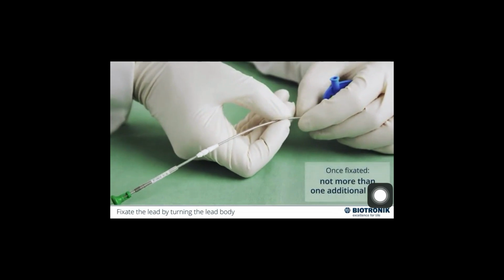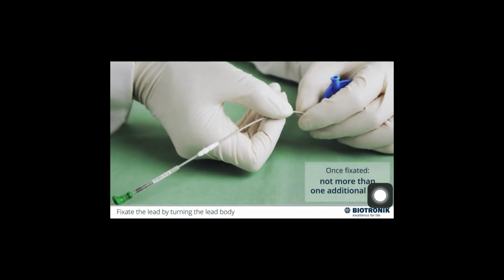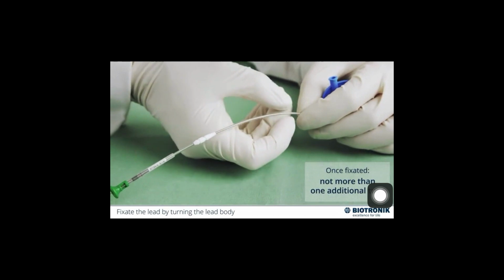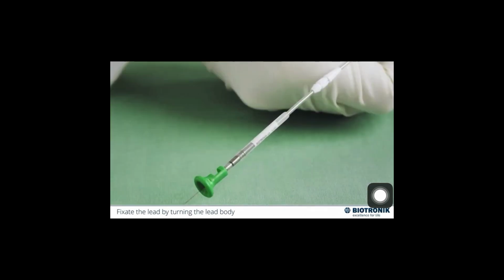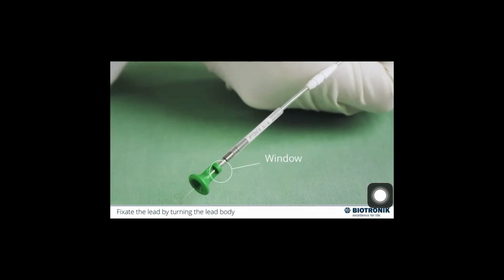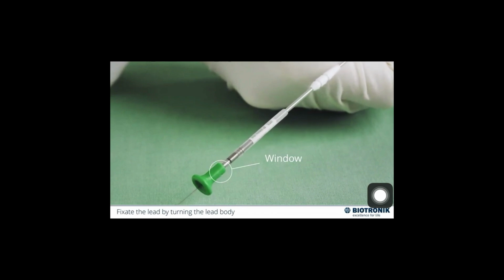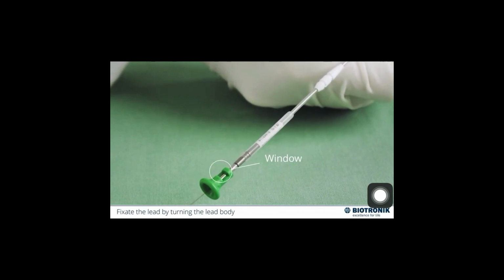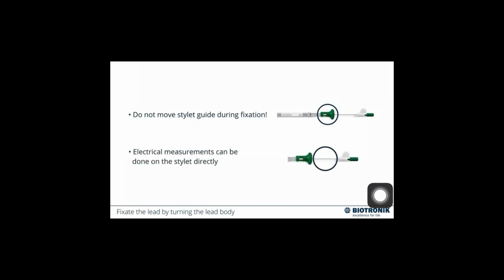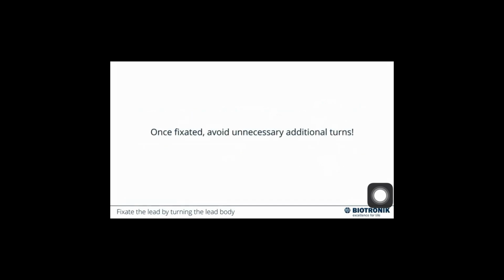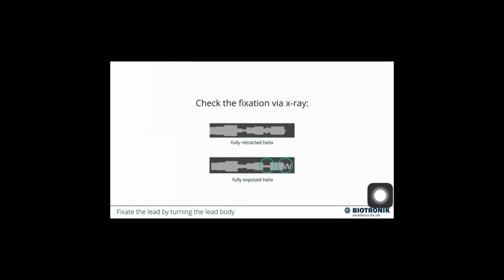Once the physician is comfortable with the lead fixation, he or she can do 1 additional complete turn, but not more. Full turns can be counted by looking at the window on the green stylet guide. In order to keep the tension on the inner coil, the stylet guide needs to be kept in place and should not be moved during lead fixation. Electrical measurements during lead fixation can be done on the stylet directly. Once the lead is fixated, avoid unnecessary additional turns.